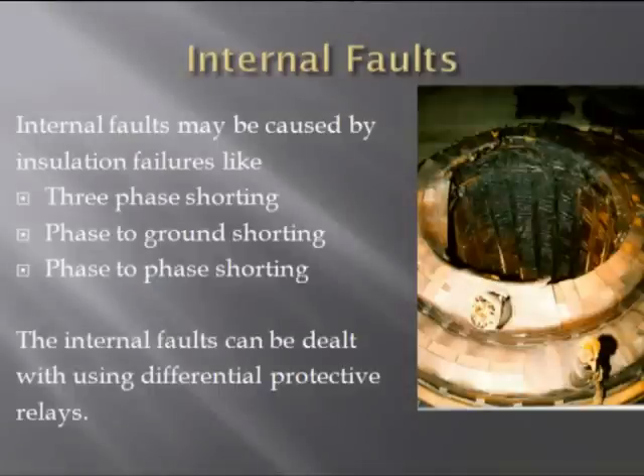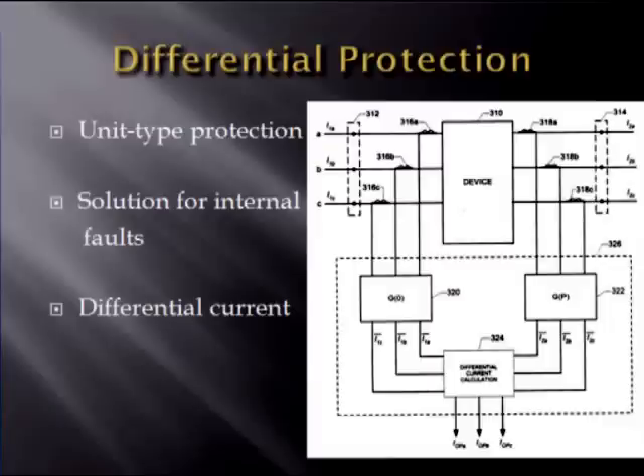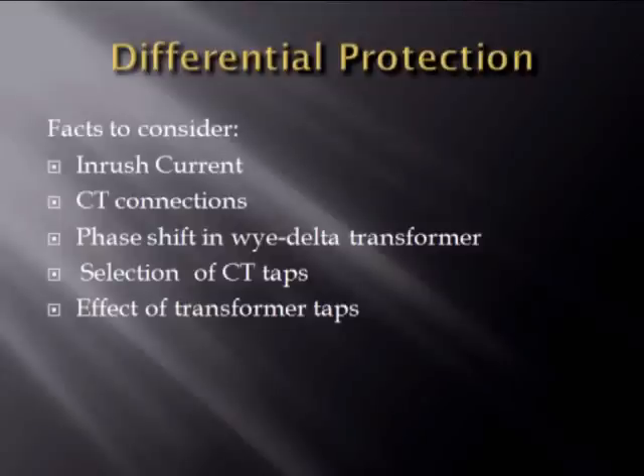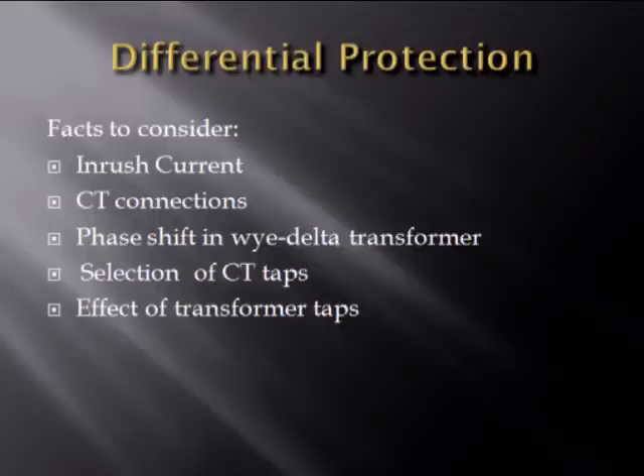Internal faults can be dealt with using differential protective relays. Differential protection is a unit type protection for a specified zone or piece of equipment — in this case, the transformer. It is used only in the case of internal faults and trips when the difference between the input current and output current is high. Key considerations for differential protection include: inrush current, current transformer connections, phase shift in Y-delta transformers, selection of CT taps, and the effect of transformer taps. Magnetizing inrush current results from any abrupt change of the magnetizing voltage, and may also be caused by an external fault. The CTs connected must cater for the phase shift between Y-to-delta transformers, so they are connected opposite to the configuration of the transformers — for example, if you have a Y-delta transformer, the CT will be connected delta-to-Y.